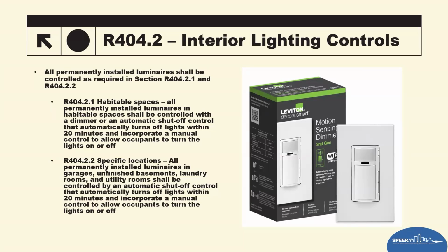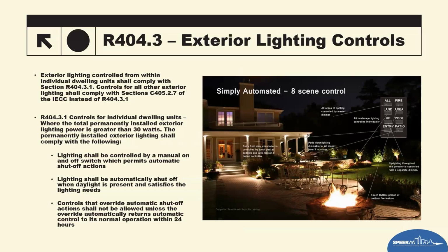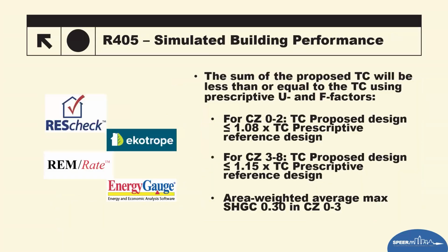They also must still have a manual override option, but it should revert back to its schedule on its own, without a manual switch having to be flipped to go back to automatic. Exterior lighting, we're still on that, but the goal is basically to prevent unnecessary time on at night. As we just said with the other one, if you have a manual override switch, it must also revert back to its originally scheduled program to save energy and not come on at night. So if you override a sensor for some reason, it should have the ability to go back to its original programming.